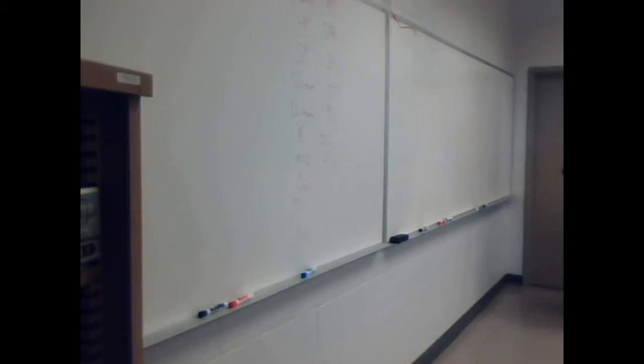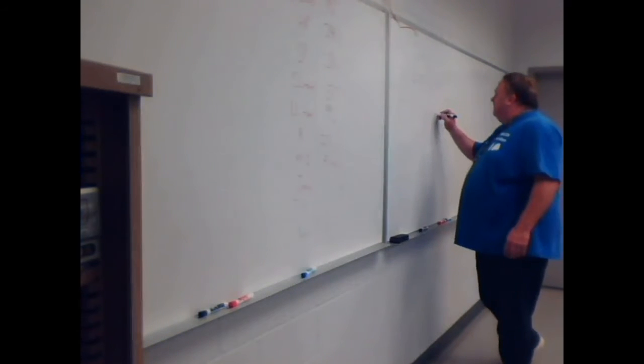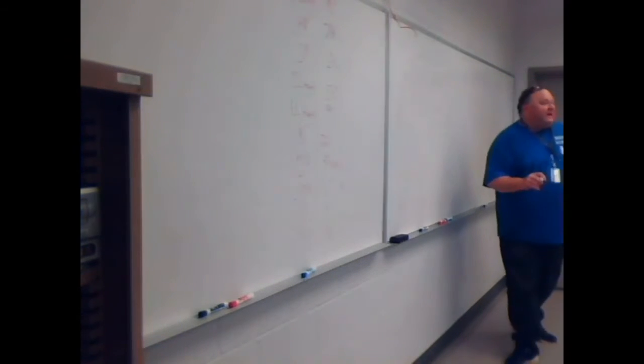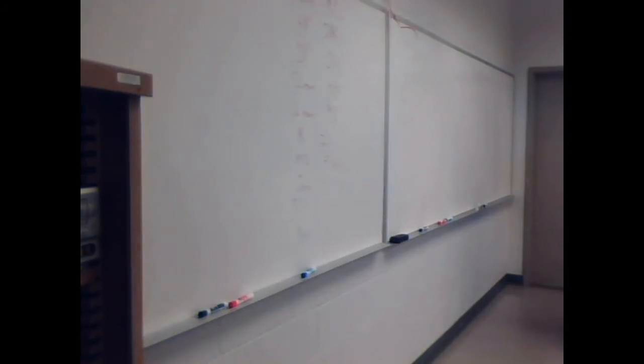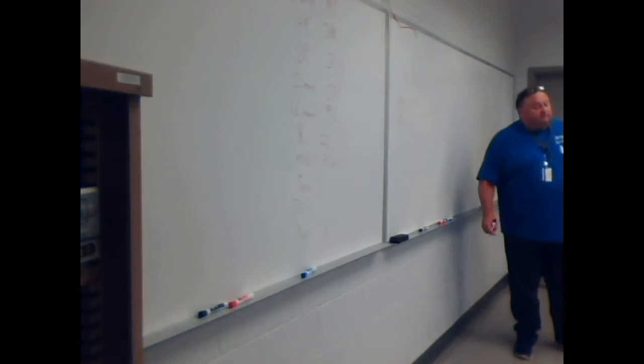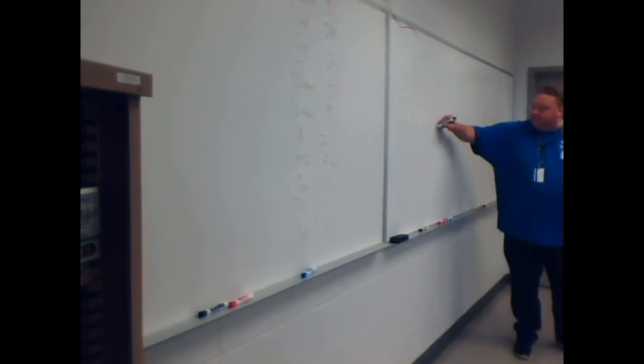Yes, 50 pounds and 50 degrees. And what was my suction pressure converted? Suction pressure was 50. That converts to about 26 degrees. That's going to equal what, 24? I expected 5 to 12. I got 24. Am I above or below my expected? I'm above it, so arrow up.